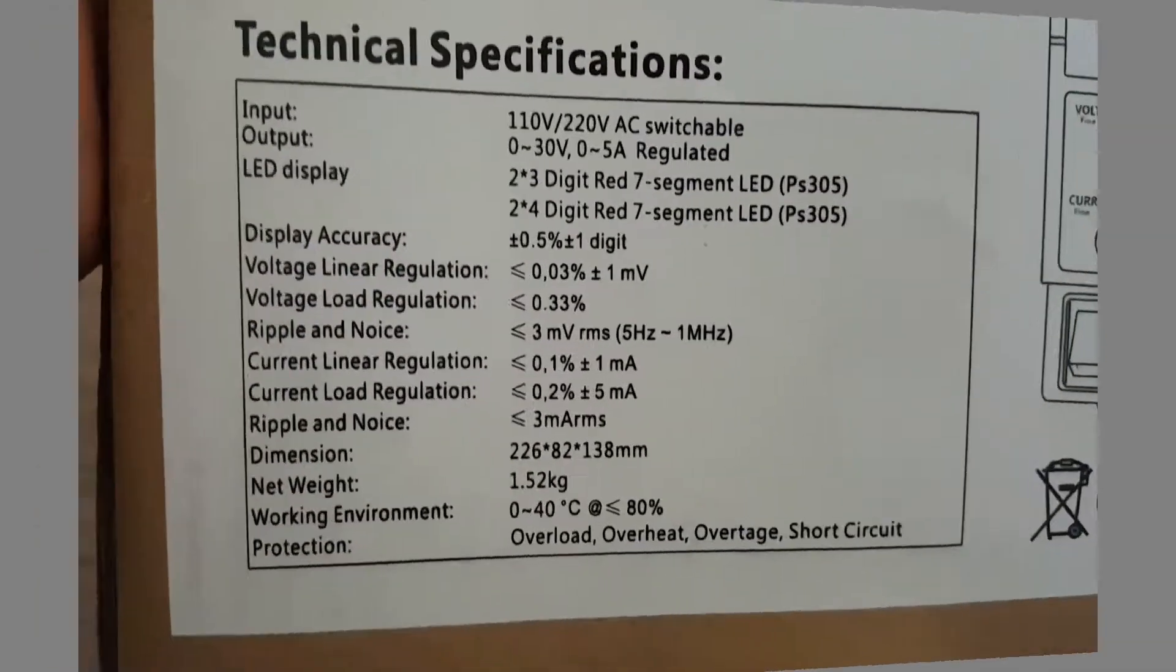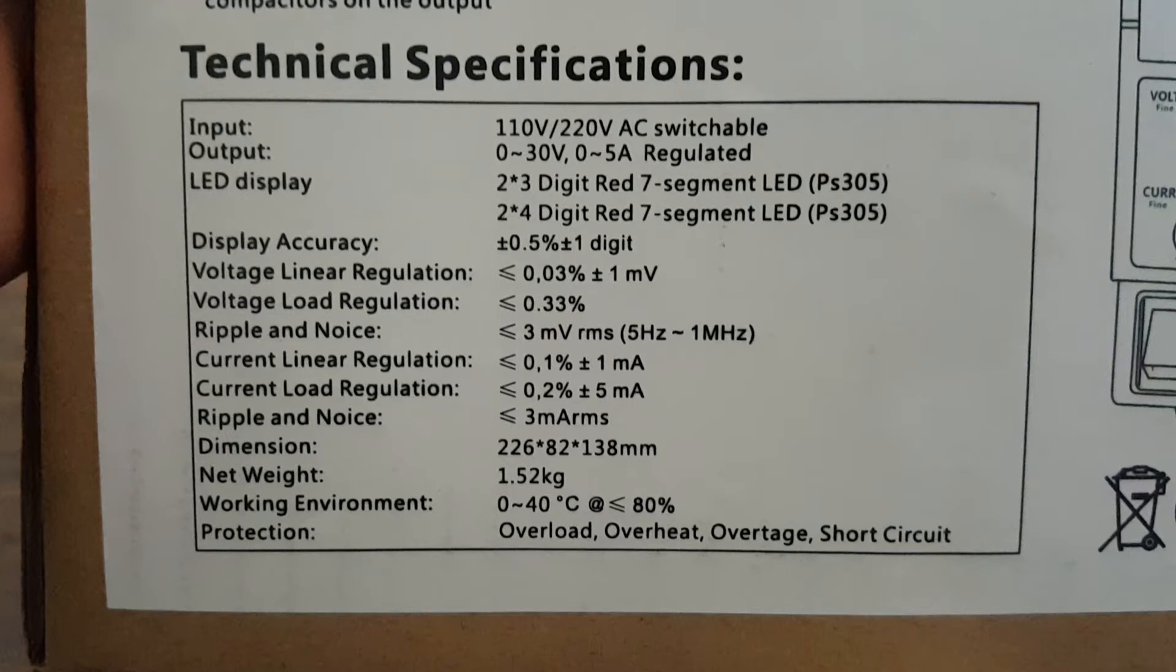So current looks good too. The accuracy does seem to be within the limits set by the specifications. We're given a display accuracy of plus or minus half a percent and plus or minus one digit, and these readings do seem to fall within that range.